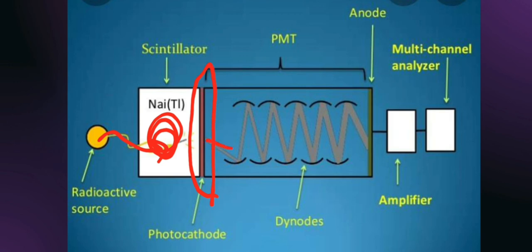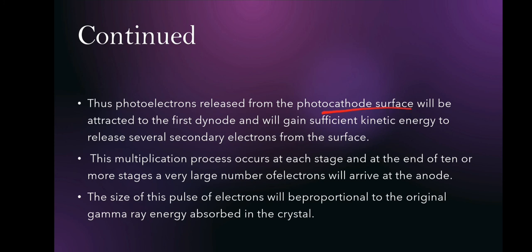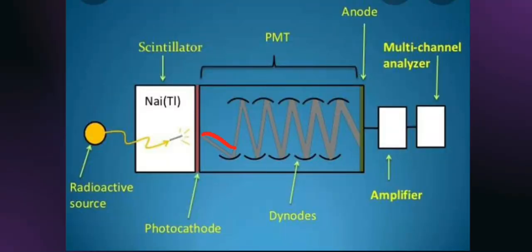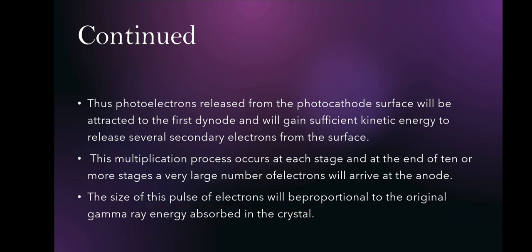The electrons released by the photocathode are attracted by the dynodes. We have a number of dynodes in series in the PMT. These dynodes are positively charged and attract the incoming electrons. The photoelectron released from the photocathode surface is attracted to the first dynode and gains sufficient kinetic energy to release several secondary electrons from its surface. Similarly, at each successive dynode, more electrons are produced, multiplying throughout the tube. The size of this pulse of electrons is proportional to the original gamma ray energy absorbed in the crystal.